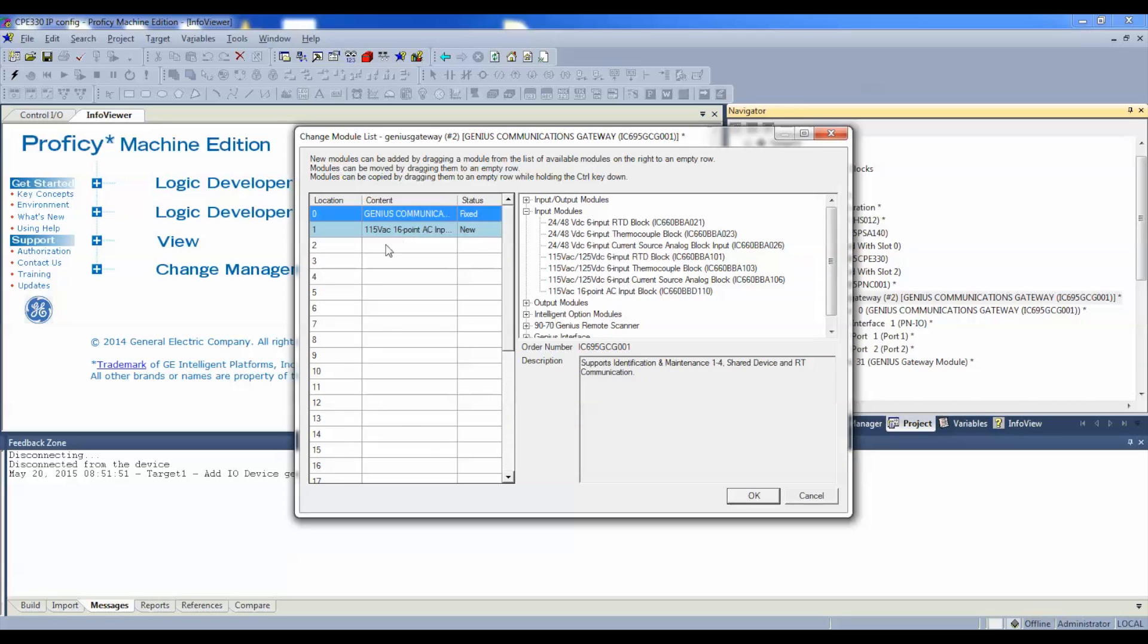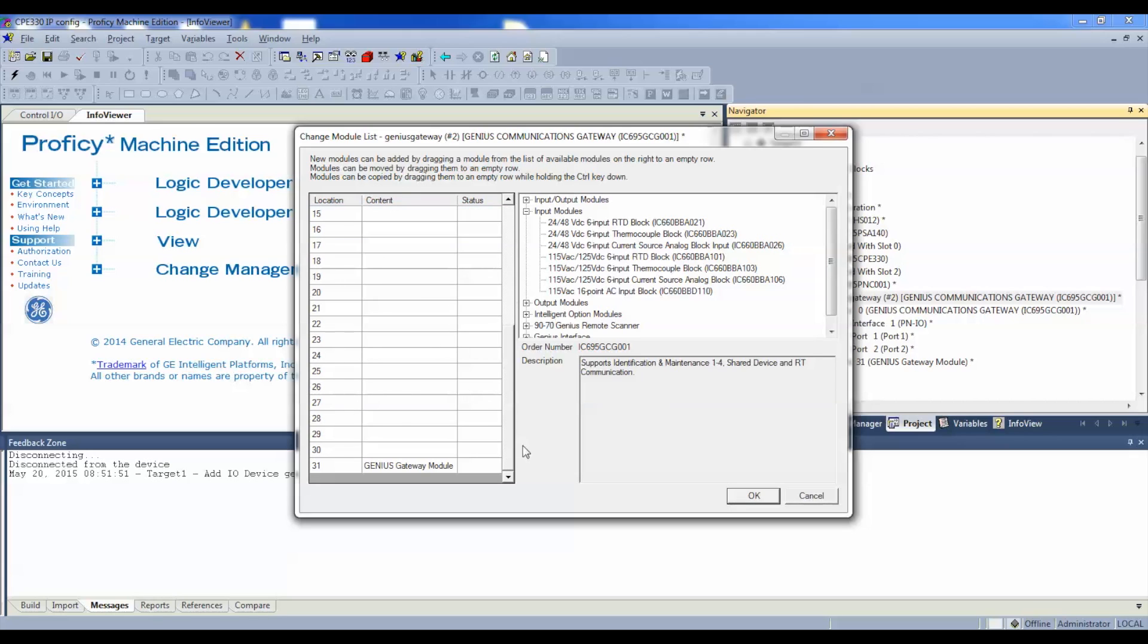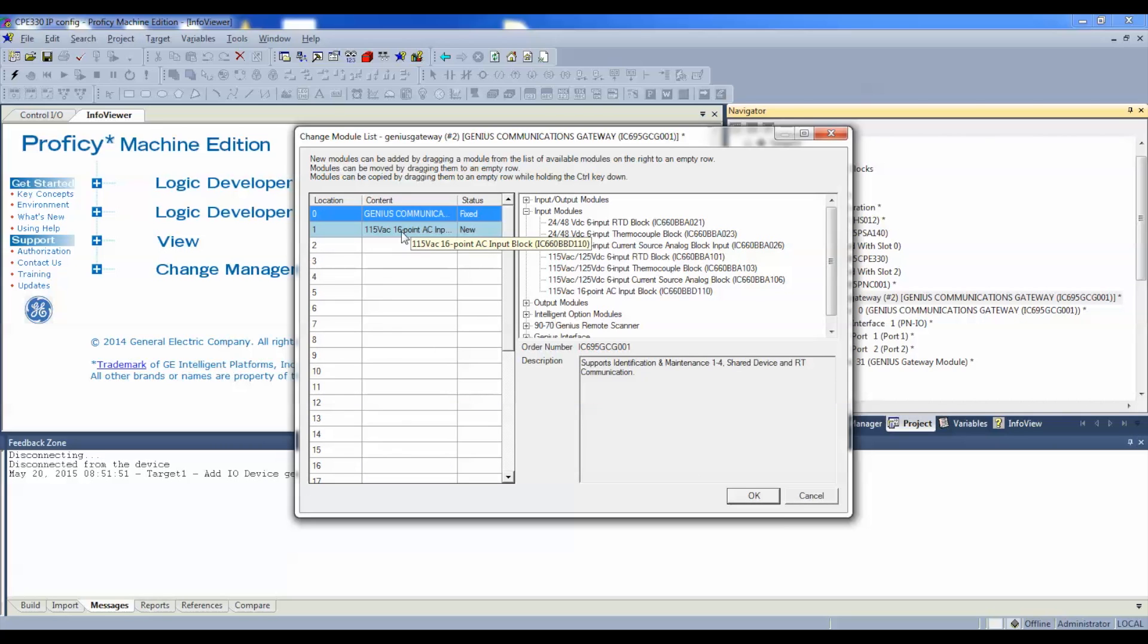Drag this over to location number one, let it go. Now if you have any other Genius devices, which I'm assuming you will, you just continue to click and drag them over, one at a time, in their proper locations, and that's obviously one through 31. Now, that's the only Genius device I'm using for this example, BBD110. It's there. I'm going to select okay.